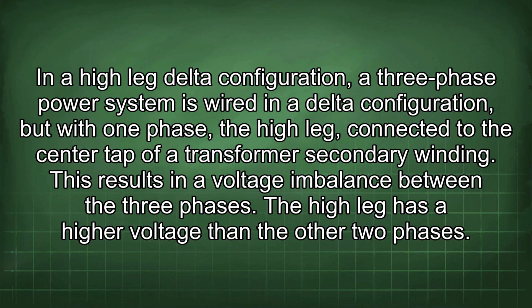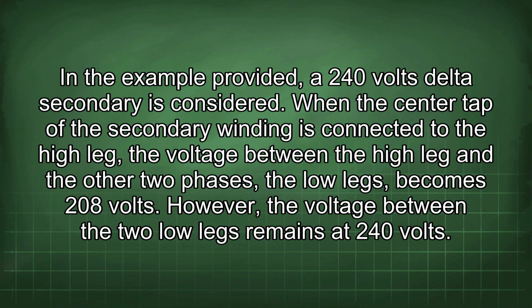In a high-leg delta configuration, a three-phase power system is wired in a delta configuration, but with one phase, the high leg, connected to the center tap of a transformer's secondary winding. This results in a voltage imbalance between the three phases. The high leg has a higher voltage than the other two phases. In the example provided, a 240 volts delta secondary is considered.